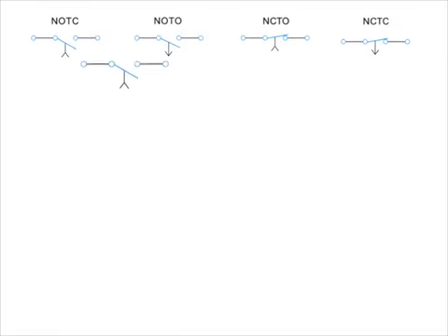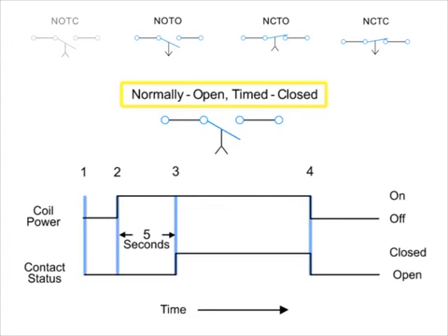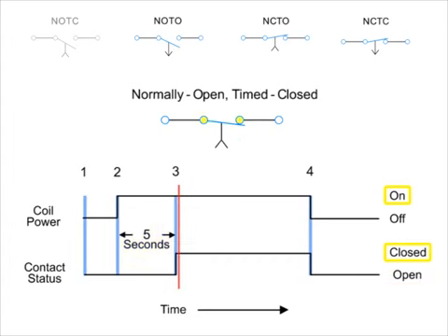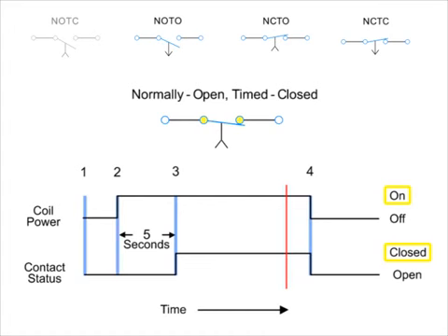First, we have the normally open, timed closed — NOTC — contact. This type of contact is normally open when the coil is unpowered or de-energized. After the coil has been continuously powered for a specified amount of time, in this example five seconds, the contact is closed. The contacts will immediately open when the coil is de-energized.